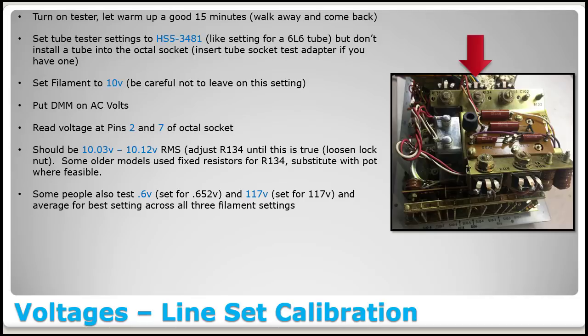I'll show you more in the video, but you're not actually adjusting this voltage. What you're adjusting is where the line set is at. If you adjust the line set to the left, then it takes more voltage to bring it up to the proper point, and thus you increase the voltage to the pins of these tubes. And you will be using R134.